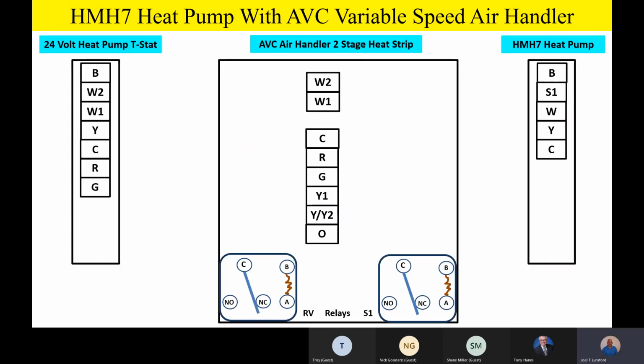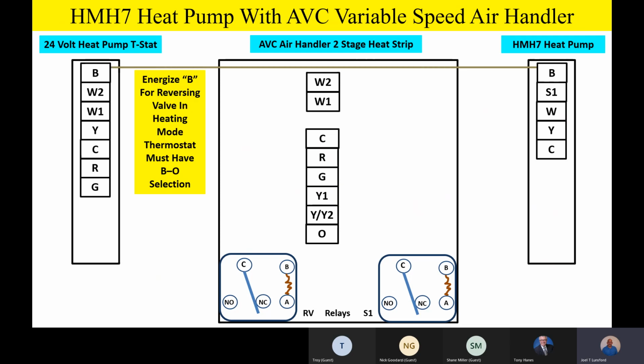So let's start out with the AVC air handler. We're going to presume that you're going to have a 2-stage heat strip in there. If you only have a single stage heat strip, then you'll just use the appropriate terminals, but we're going to utilize a 2-stage heat strip just for fun. And we're going to take that B terminal straight outside, just like we did before. Nothing changes. The only difference between the low voltage wiring on this product is the fact that we do have an O signal, an O terminal, and we have that RV relay we're going to have to deal with.